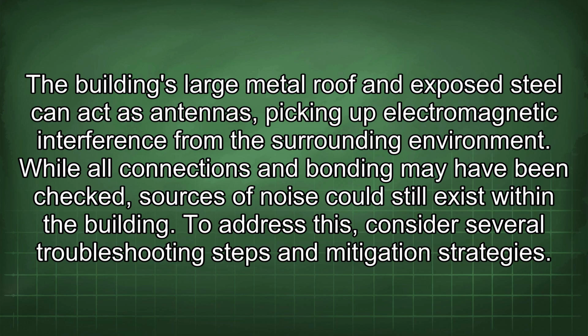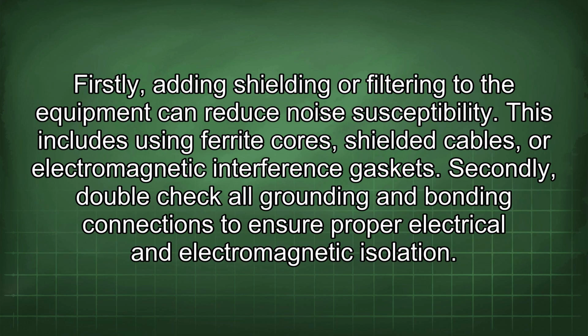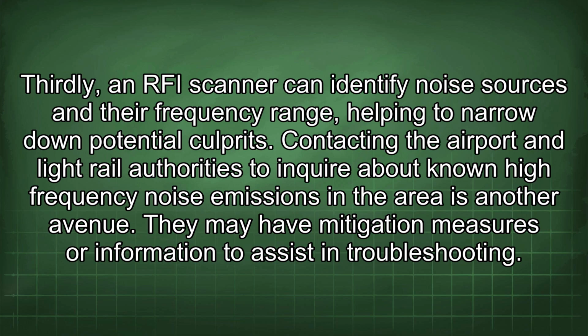While all connections and bonding may have been checked, sources of noise could still exist within the building. To address this, consider several troubleshooting steps and mitigation strategies. Firstly, adding shielding or filtering to the equipment can reduce noise susceptibility. This includes using ferrite cores, shielded cables, or electromagnetic interference gaskets. Secondly, double-check all grounding and bonding connections to ensure proper electrical and electromagnetic isolation. Thirdly, an RFI scanner can identify noise sources and their frequency range, helping to narrow down potential culprits.